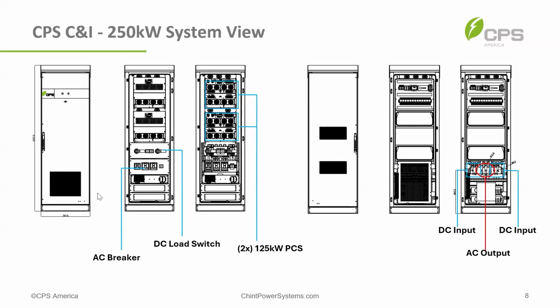Essentially what I was talking about previously is whenever you are doing an install where you want to have a microgrid, independent from the grid itself, you're going to need an isolation transformer. The reason is our system, and pretty much every other C&I system out there, outputs a 480 delta, so essentially the output looks like a triangle if you were to draw it out. With that, there's no neutral point, so you need what we call an isolation transformer, which in most scenarios would be a delta to Y.